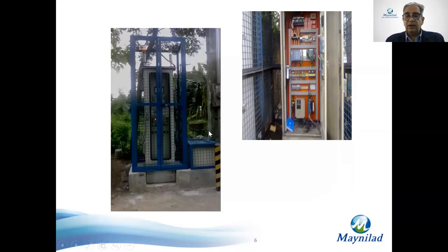These pumps and valves sit below the surface. There's a manhole here, and below that you usually have about 3 or 4 pumps and about 6 to 8 valves and instruments. The idea is that this is what we call a booster station—it boosts the pressure along a certain area of the network, in order to give sufficient supply. This normally operates autonomously; there's a program in it that controls, based on certain logic, which valves and pumps turn on, et cetera.